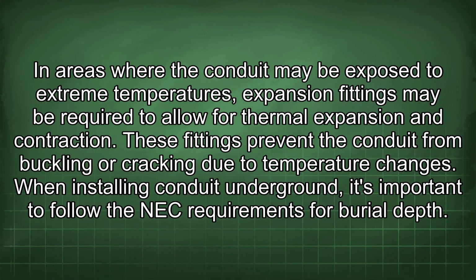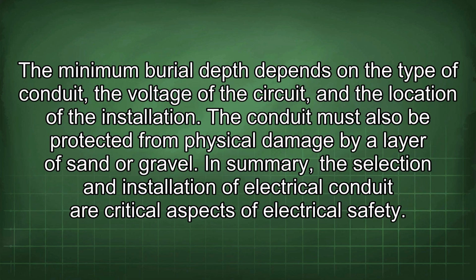When installing conduit underground, it's important to follow the NEC requirements for burial depth. The minimum burial depth depends on the type of conduit, the voltage of the circuit, and the location of the installation. The conduit must also be protected from physical damage by a layer of sand or gravel.